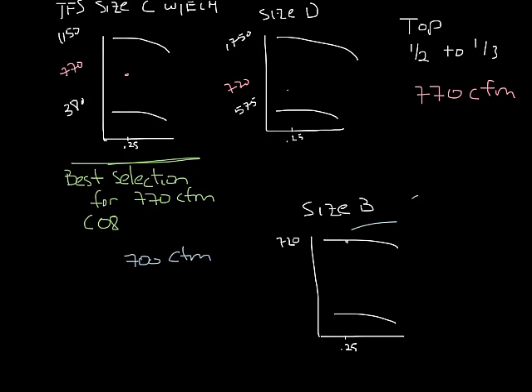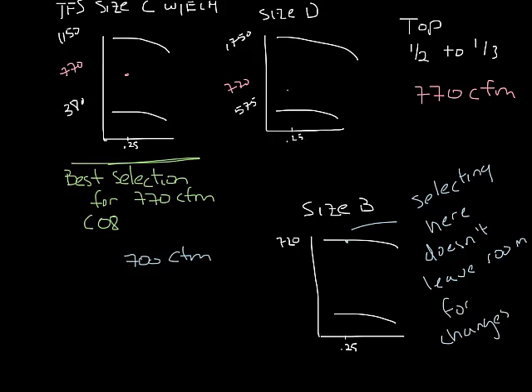But in this case, you would be right at the top of the fan curve. Selecting here doesn't give you much leeway in case the pressures are higher than expected or your airflow requirements change.